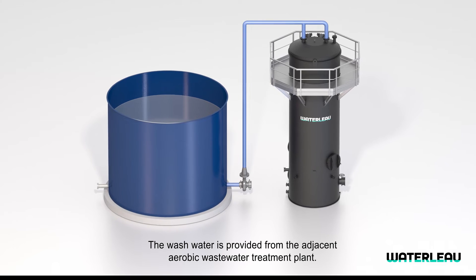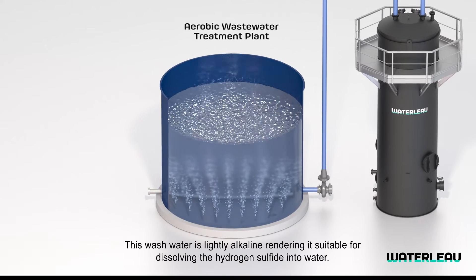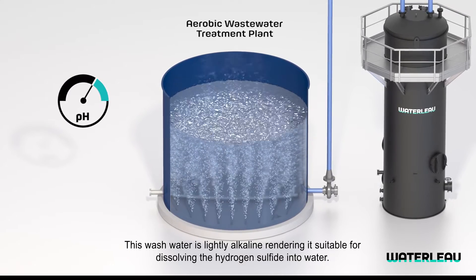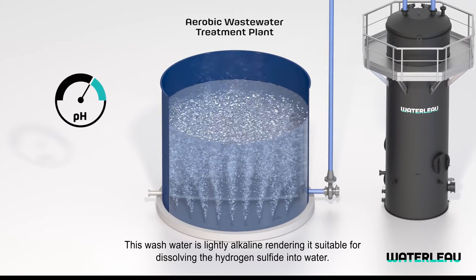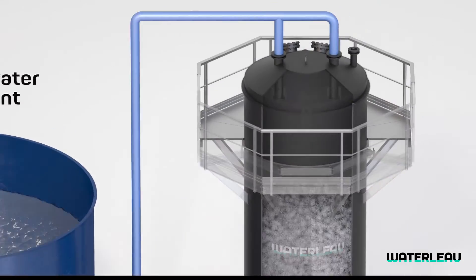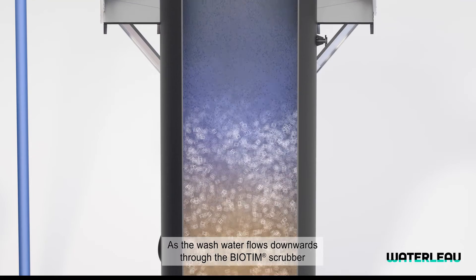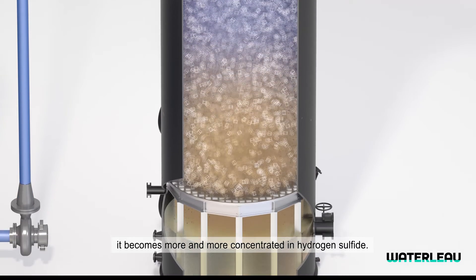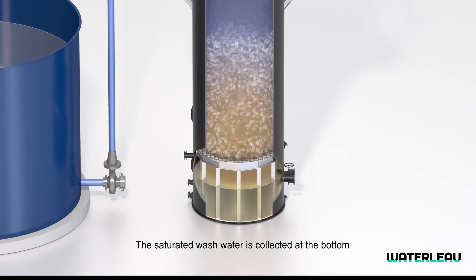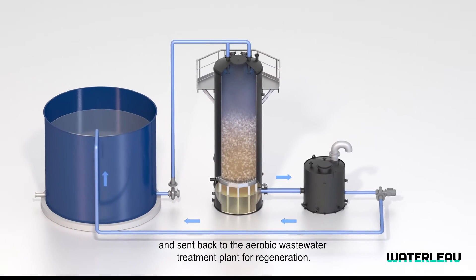The wash water is provided from the adjacent aerobic wastewater treatment plant. This wash water is lightly alkaline, rendering it suitable for dissolving the hydrogen sulfide into water and almost free of cost. As the wash water flows downwards through the Biotim Scrubber, it becomes more and more concentrated in hydrogen sulfide. The saturated wash water is collected at the bottom and sent back to the aerobic wastewater treatment plant for regeneration.